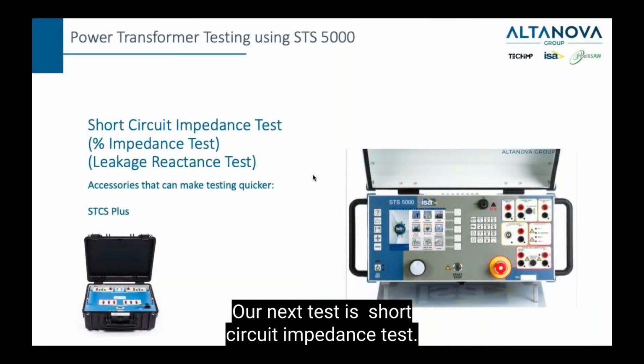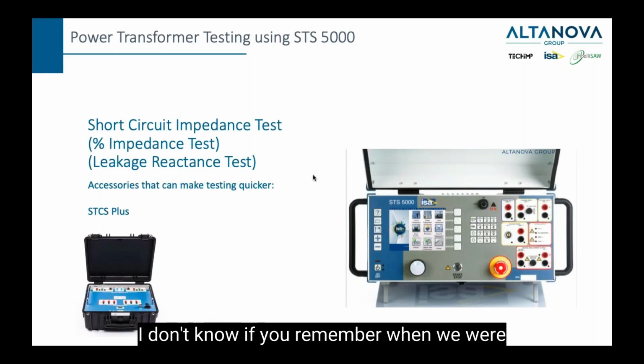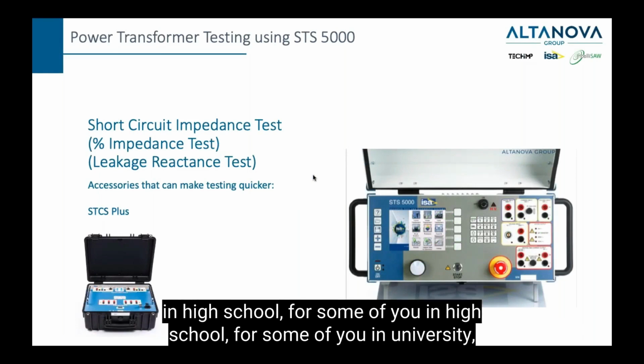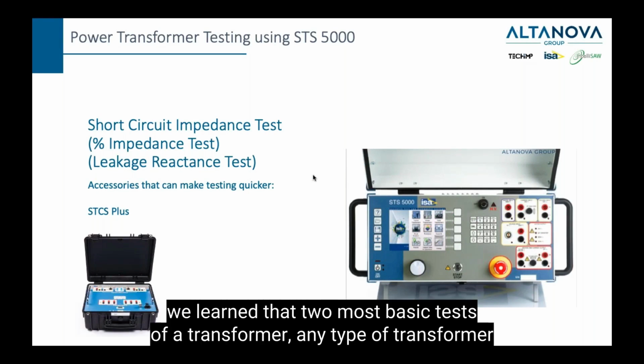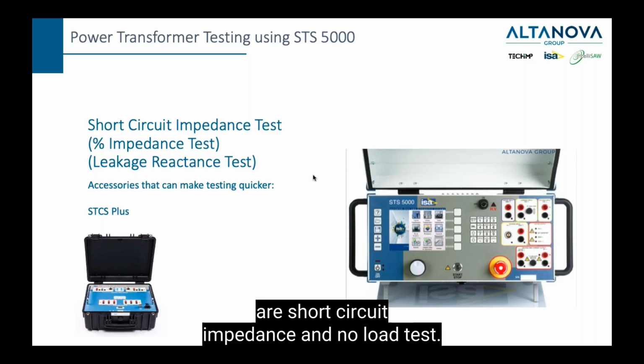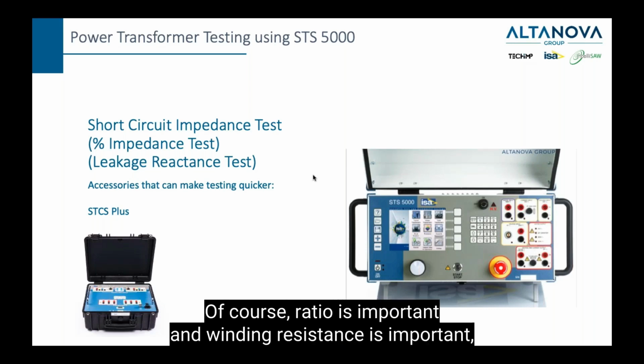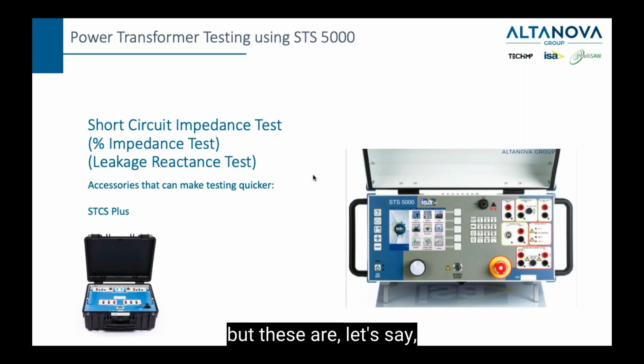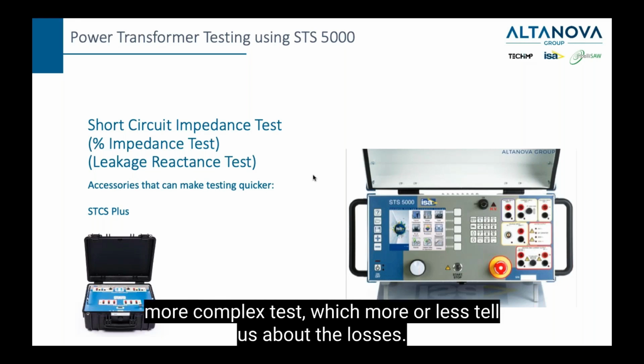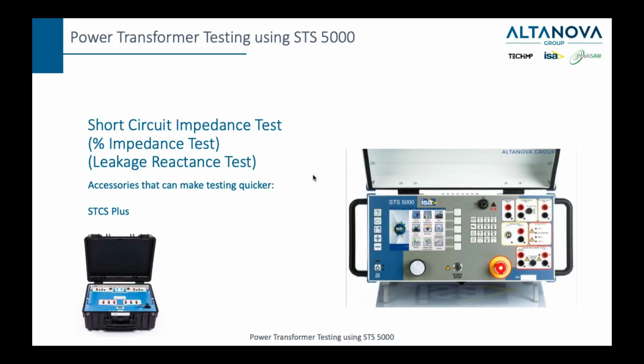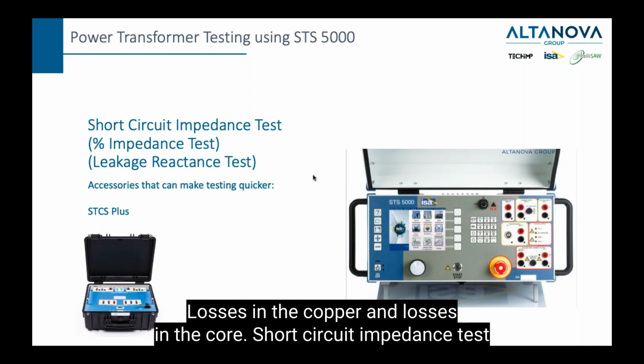Next test is a short circuit impedance test. I don't know if you remember when we were in high school, for some of you in university, we learned that the two most basic tests of a transformer, any type of transformer, are short circuit impedance and no load test. Of course, ratio is important and winding resistance is important, but these are, let's say, more complex tests which more or less tell us about the losses in the copper and losses in the core.